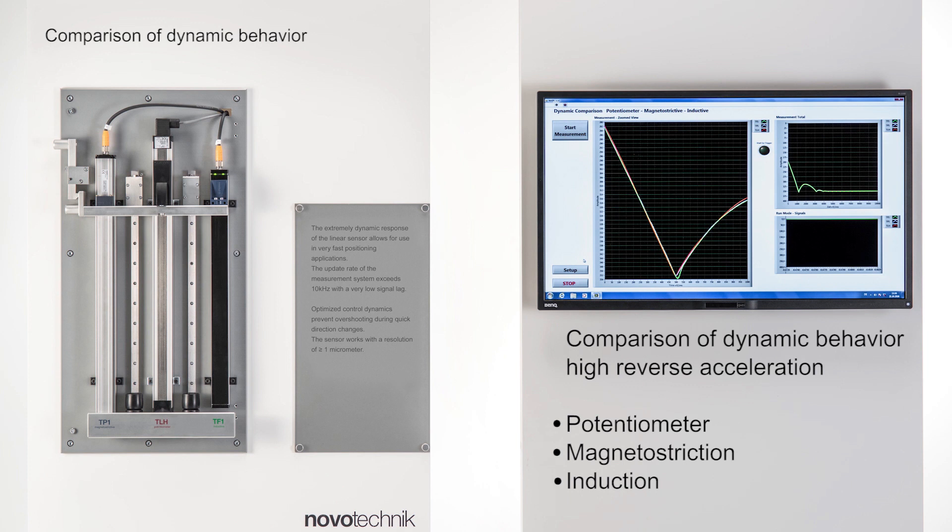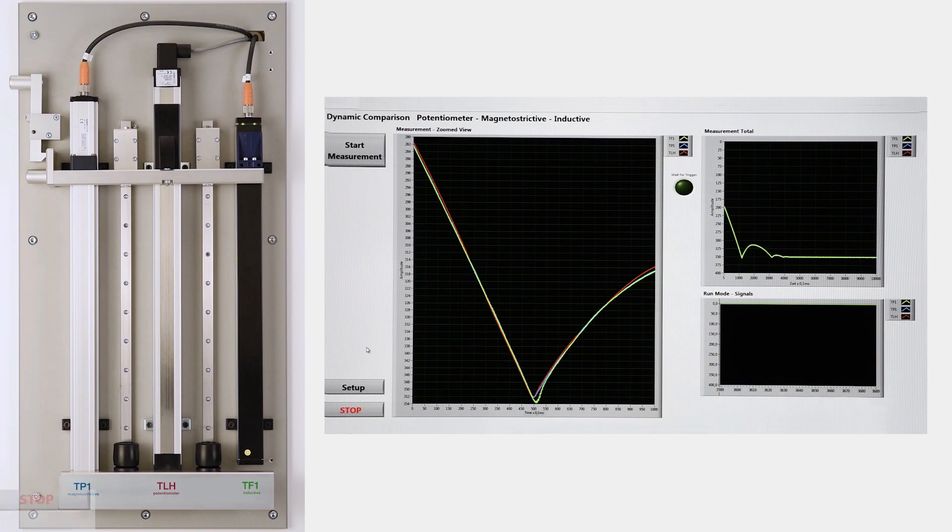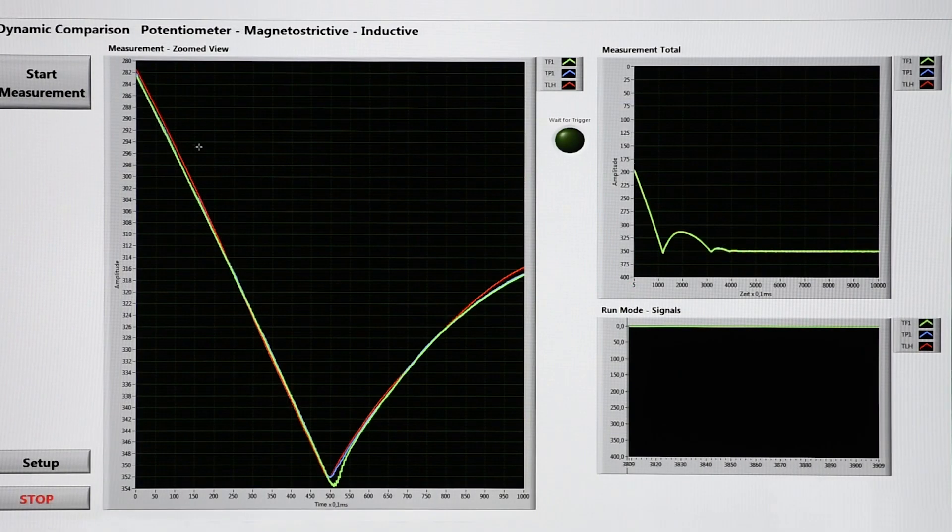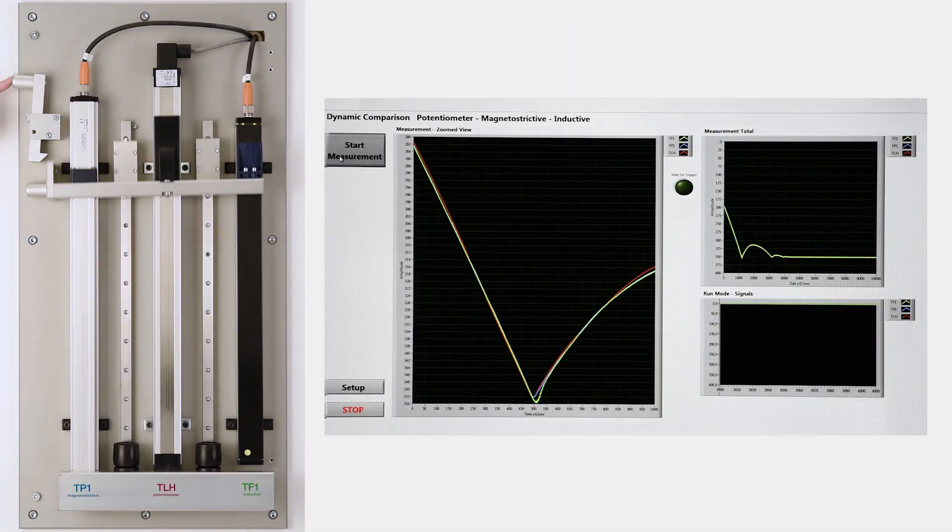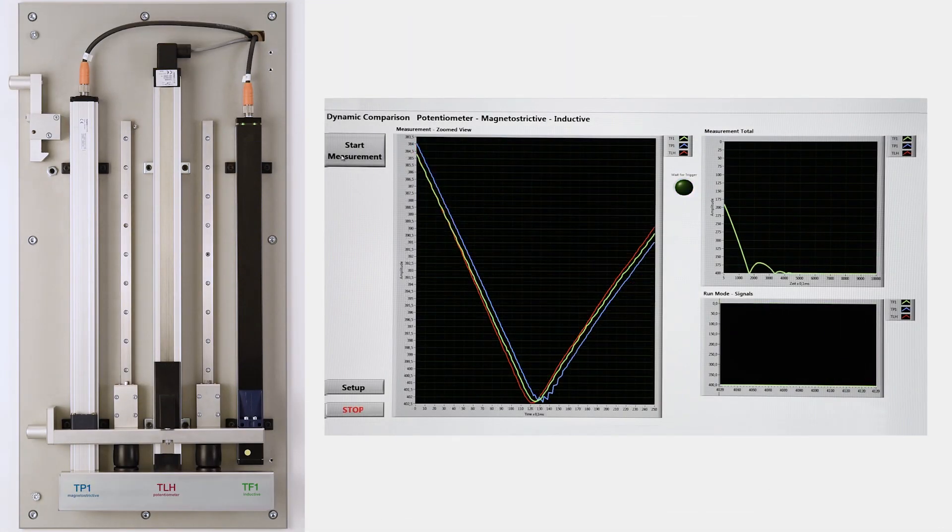The potentiometer provides real-time position measurement limited only by the bandwidth of a signal conditioning circuit. The magnetostrictive principle shows an inherent and relevant propagation delay being based on the time-of-flight principle of a mechanical wave in a wire.